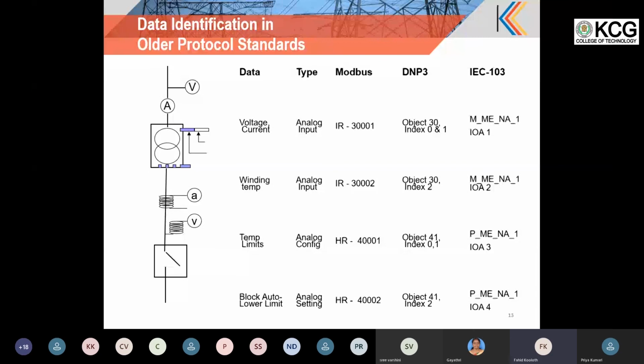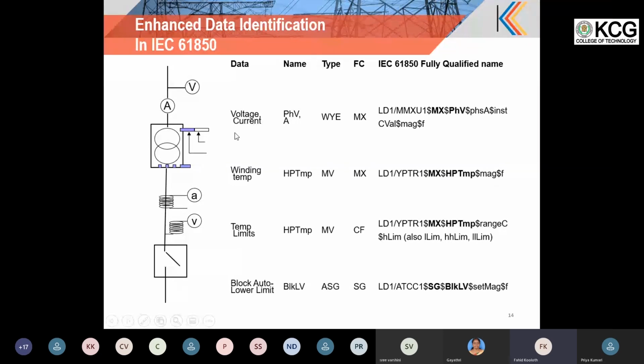Whereas in 61850 you can see this is a measurement logical node that achieves the functionality of measurement, which is called MMXU, and PhV is phase voltage, and it is phase A instantaneous value. So it is measurement, phase voltage, phase A instantaneous value. So voltage from phase A will be represented like this in any vendor system. If we connect with the IP address and get this tag from a system, we can understand this is a phase voltage, phase A, irrespective of which vendor it is taken from. This will be common. Similarly, for any data, a similar methodology is adopted. So complete data identification and data modeling is done in 61850.